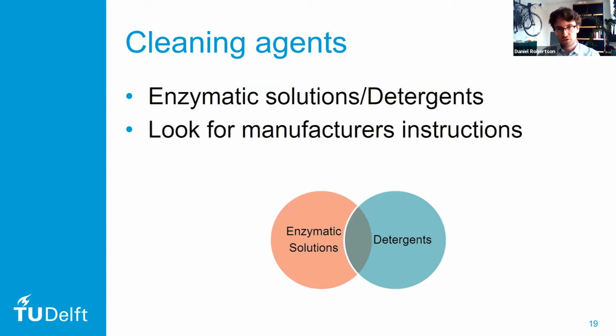Now, the other ones are the detergents, which are more like soap. And these soaps make it easier for the water and the enzymes to penetrate into the dirt that's on the surface of the instrument. Now, one important thing is that these cleaners are not disinfectants. They are there to get all of the debris off, but they don't actually kill any of the microorganisms. So after cleaning, you still have to be very careful about infection.